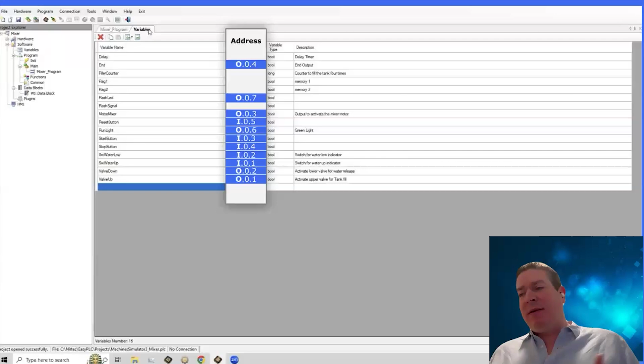To do this, you compile these programs and transfer them to the PLC. You can push and pull from a PLC with what I call self-describing software. The more complex versions tell you what devices they're wired up to, the available memory, the power, the processors — it describes all that and how the machine is supposed to work. So you can always pull what that software is, but you can also push to it.